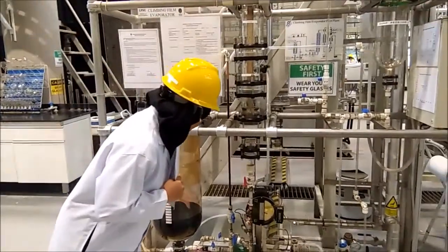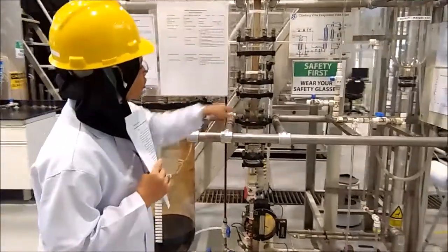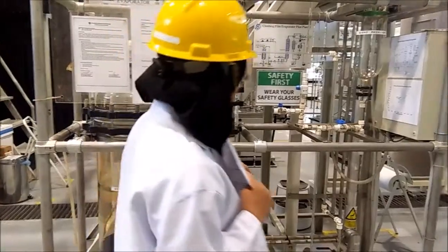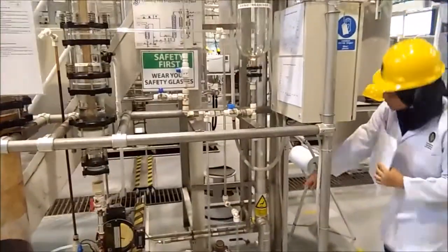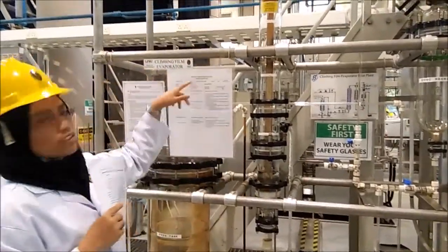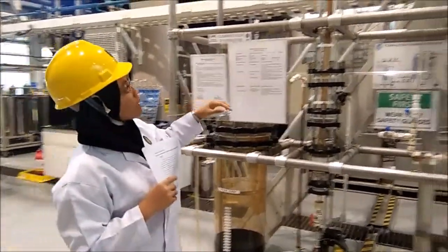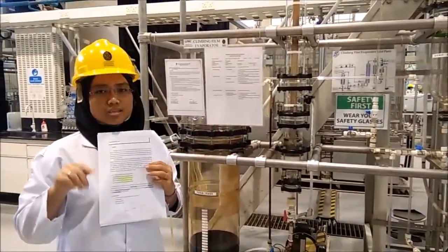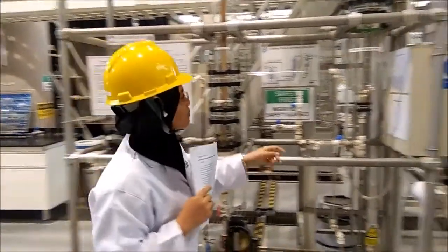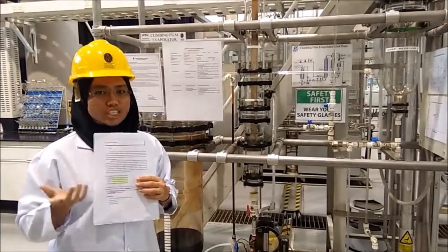First, we need to open valves V2, V3, and V5 to allow the feed from the tank into this evaporator. Next, we close the first valve and open the steam valve to allow the hot water into this evaporator. After that, we need to observe the first and second bubble forming and record the time taken. Then we wait 20 minutes to collect the samples of concentrate, condensate, and evaporate. We measure the refractive index as well as the volume of the solution.